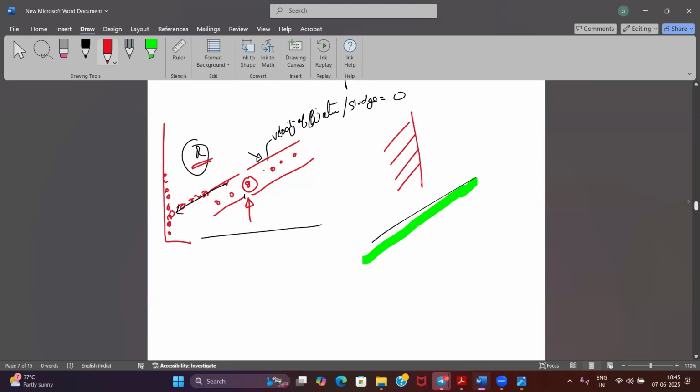I told you, when it was here at this point, throughput was acting. So this is throughput, this is centrifugal force, and this will be the resultant. But now when it reaches over here, throughput is no longer acting. So I only have the centripetal force pushing the clean oil inward, and the centrifugal force pushing the heavier particles outside, but it will flow towards the resultant.